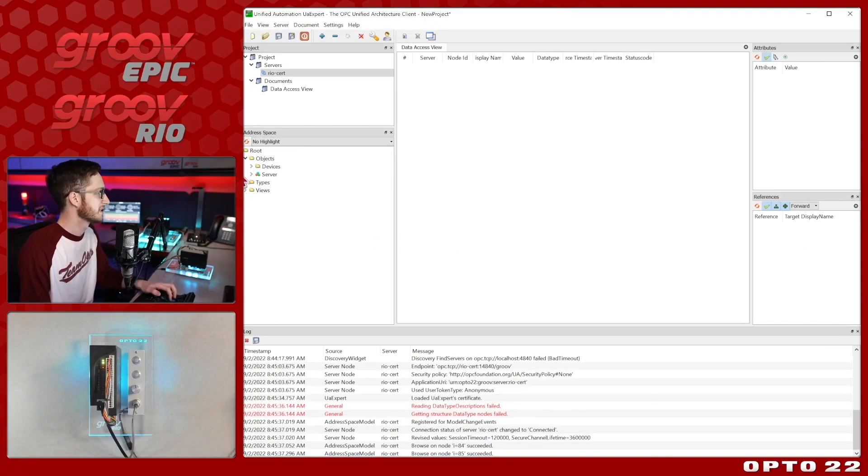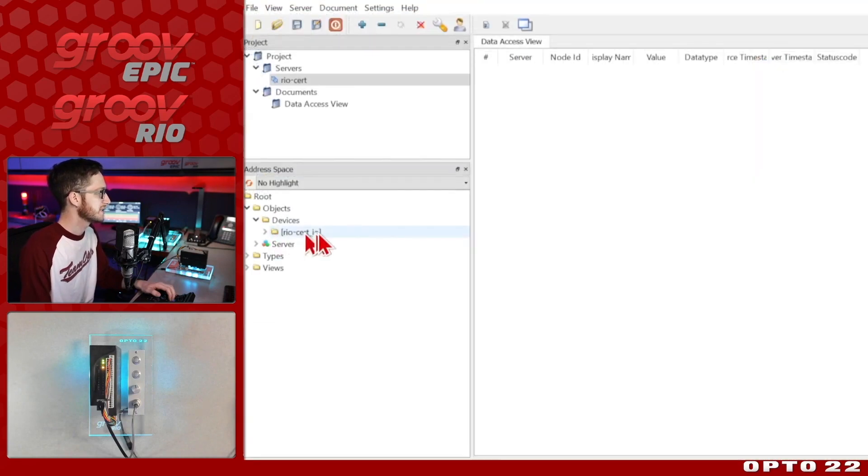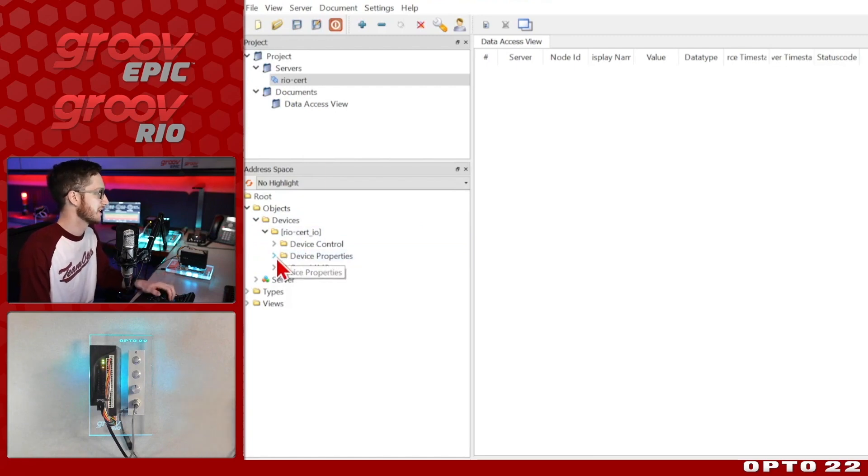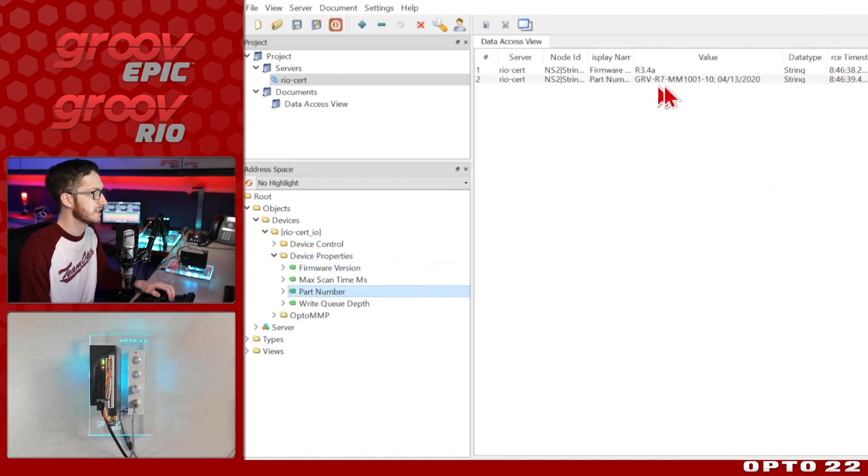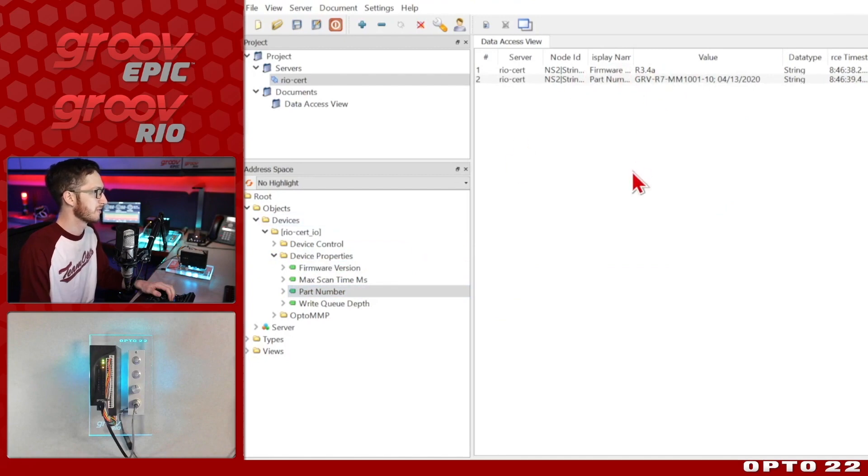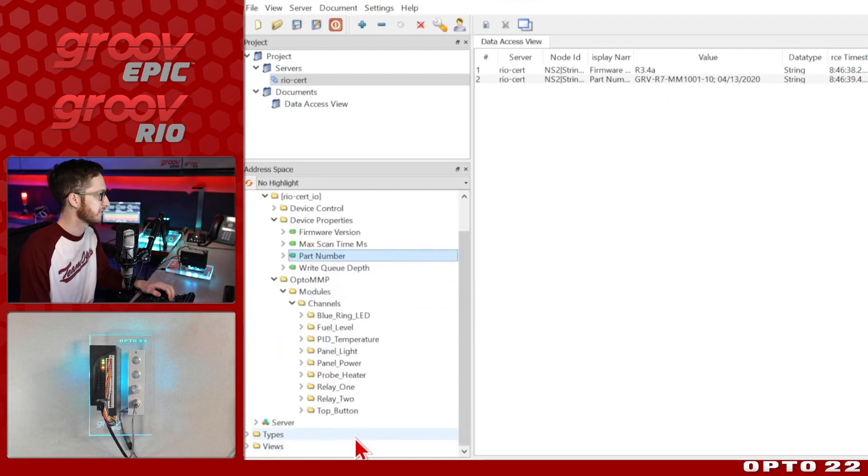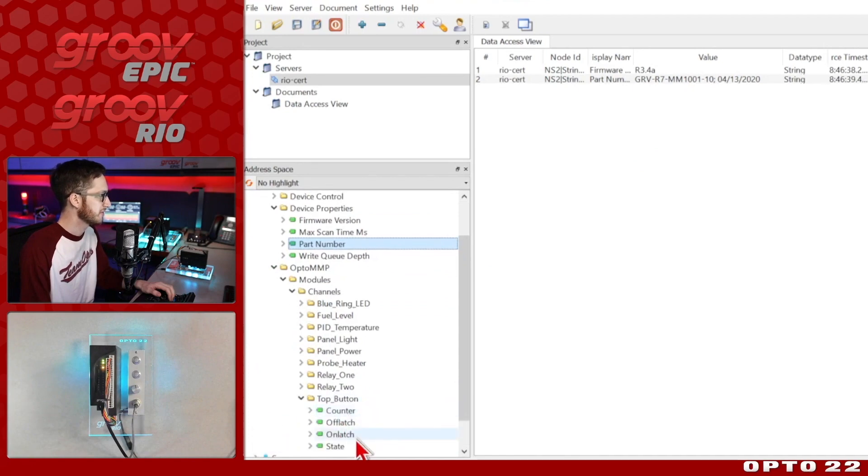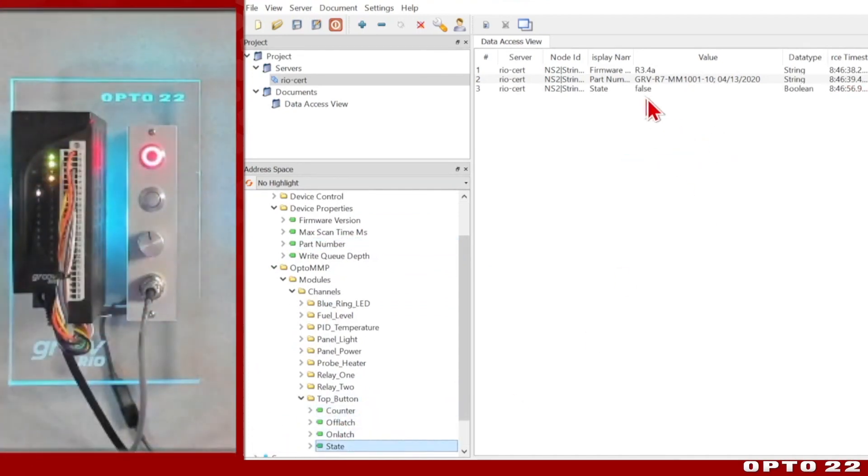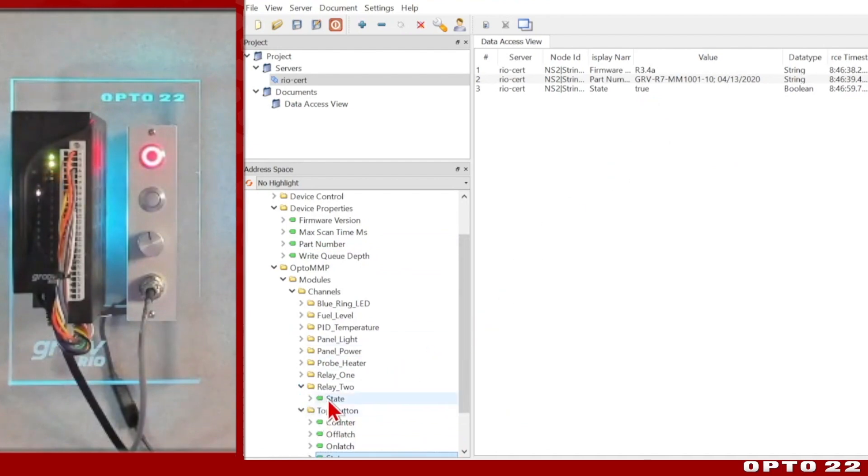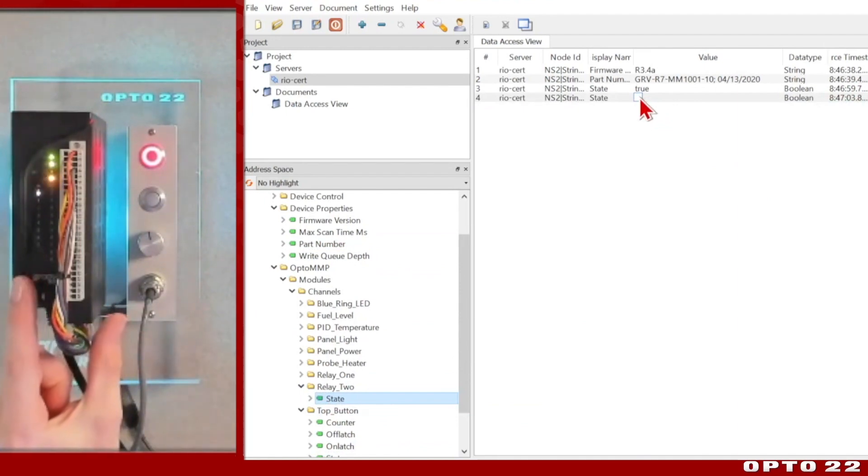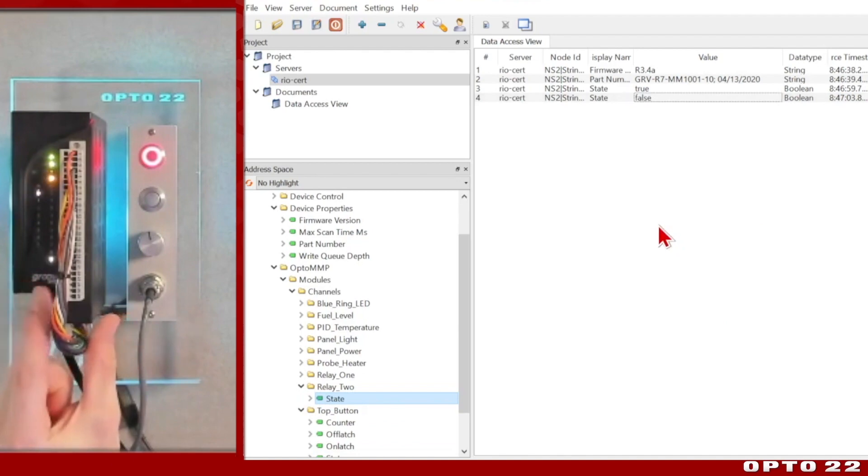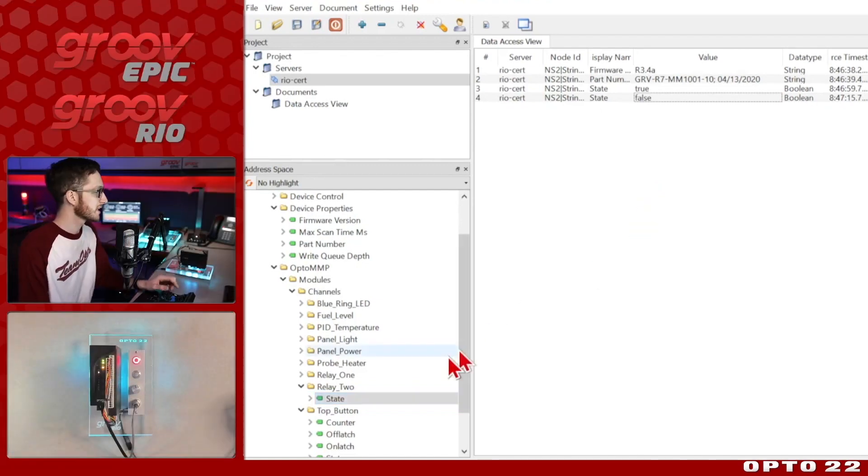So now that I'm connected, we can drop down our objects, look at our devices, and you see right there's that rio-cert IO. So under that, I have a bunch of different data points. I have my device properties, where I can check out my firmware version or my part number. We can expand that out and see that I do have a groov RIO MM1, as well as the current firmware version 3.4a. Below that, I have OptoMMP with my single module and all of the channels that I have configured right now. So you can see I have this top button. If I drag in the state of that, you can see that it's currently false. If I toggle it on, we'll see it switch to true. If I were to grab a relay and drag the state in, because I enabled writes, I can double select this. If I check it on, we'll see this LED turn on for the channel here. And there it goes, it just turned on. And off again. There we go. So we clearly have a bi-directional connection to the IO here.